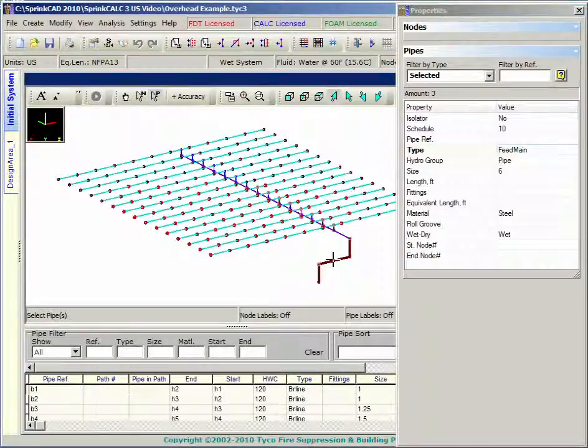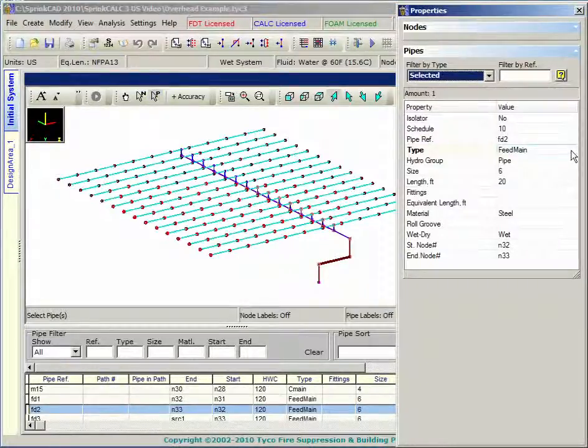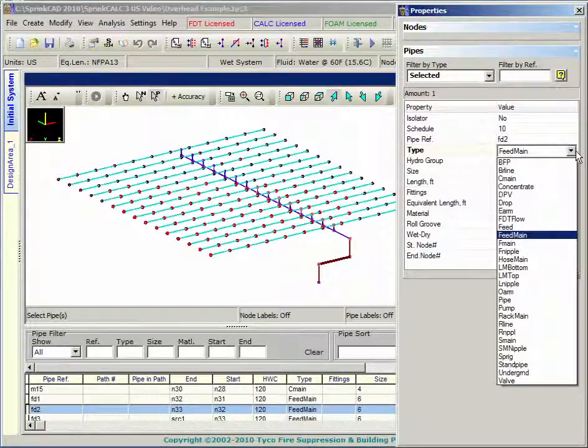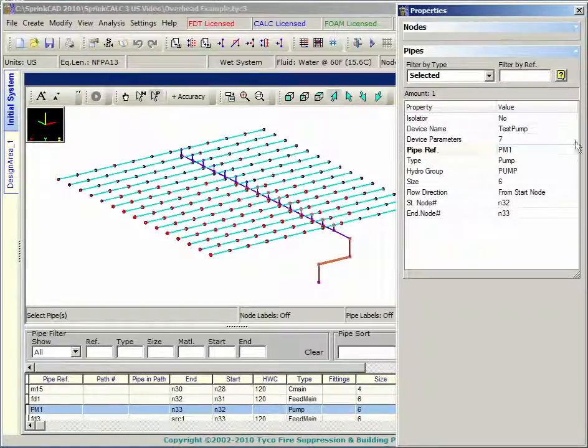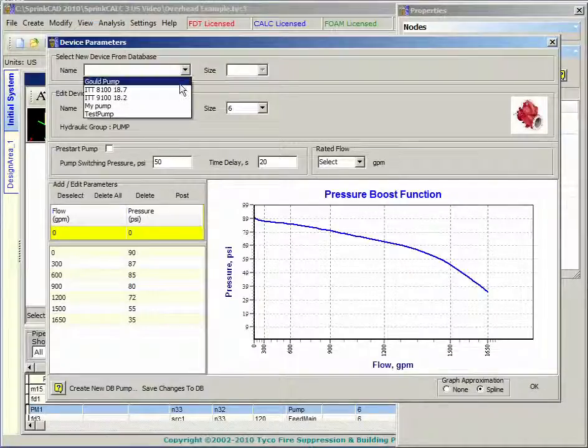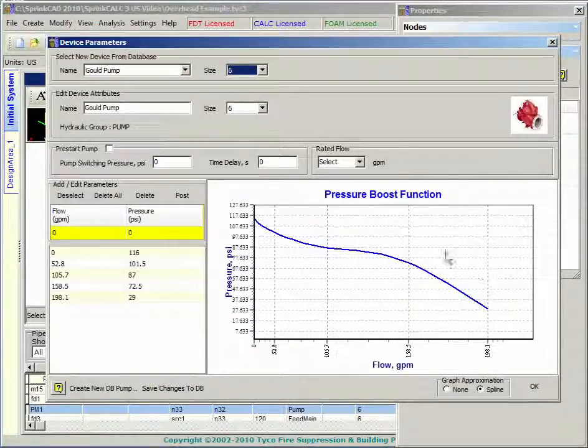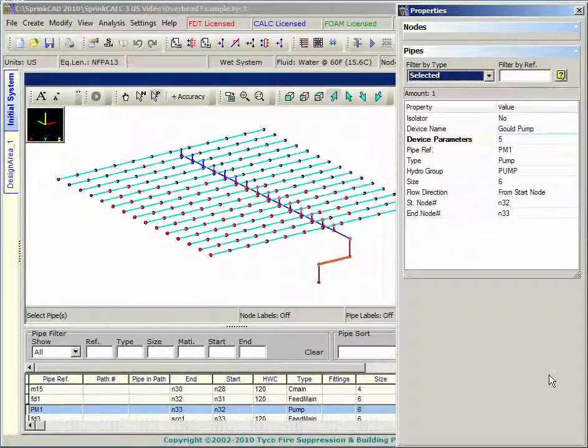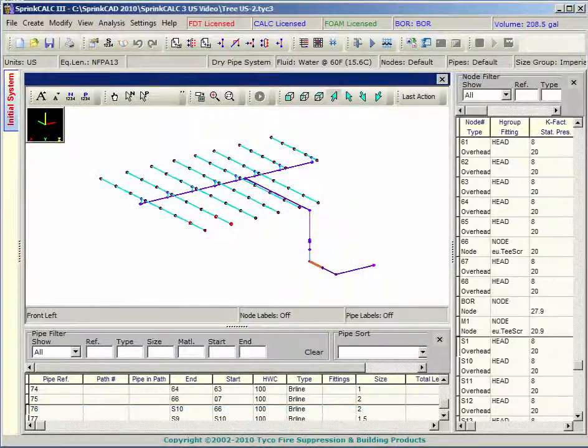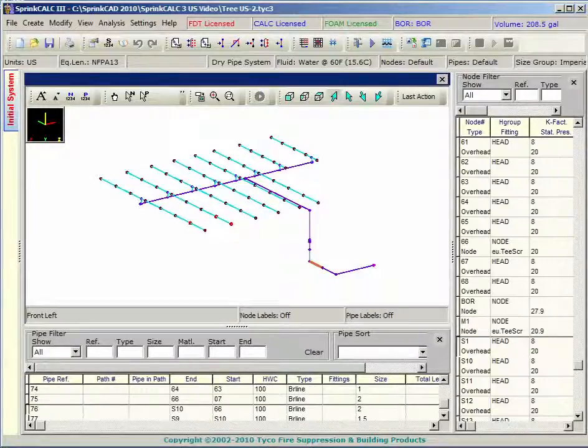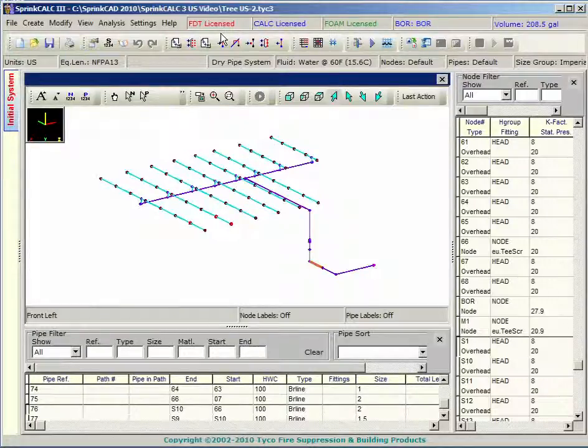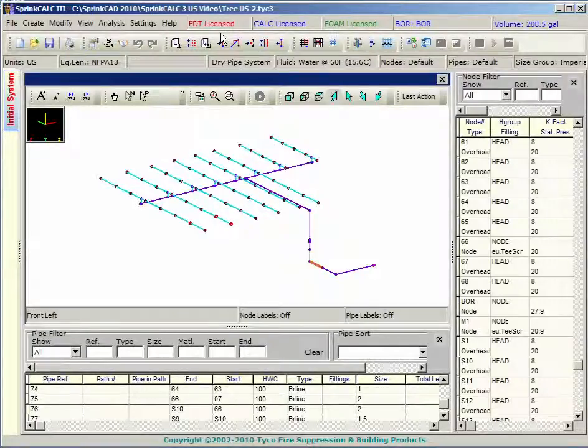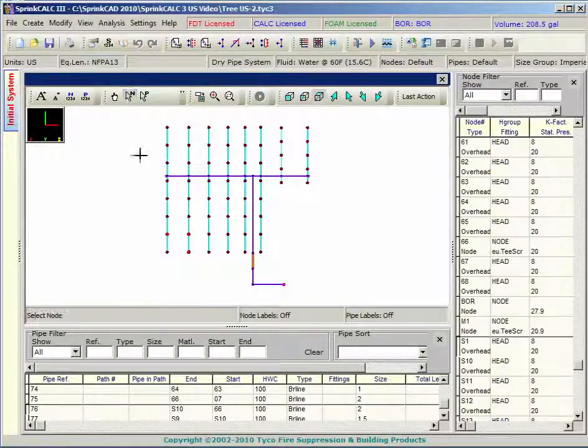You can also view and edit items such as pumps and water supply nodes. The program must be licensed with Sprink FDT in order to run fluid delivery time calculations. Your system must have a dry pipe valve and a water supply node. Both of these may be edited through the properties dialog box.